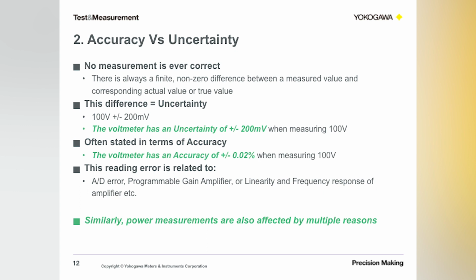So every measurement will have some type of an error, and usually comes from either the analog front end or the A to D converter or a programmable gain amplifier, or even the linearity and the frequency response of that amplifier, or all of them. The example I just gave you is a simple example of measuring voltage. Power measurements, on the other hand, also are affected by the same reasons and a few more. So to better understand this, let's first take a look at how power is measured, right?